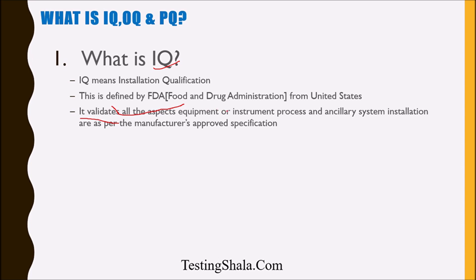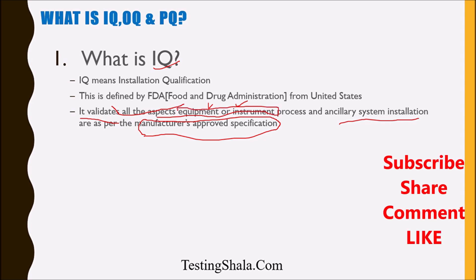The main thing we are going to validate in Installation Qualification is to ensure that whatever instrument, equipment, or software we are going to install is as per the manufacturer's approved specification. The manufacturer's approved specification is approved by the FDA, and the FDA ensures that this kind of Installation Qualification has to be done to verify that it meets FDA standards.